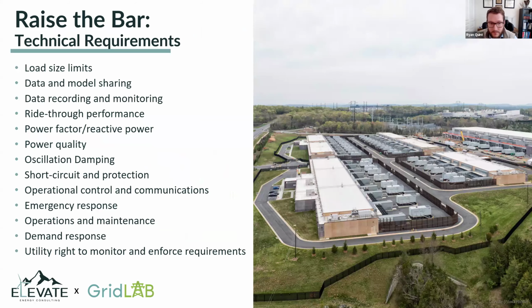Next slide. One thing we're really focused on, and were actually rather surprised by during our research, is the need to develop technical requirements for large loads. In our industry, imposing requirements on customers was, in the past, unfathomable for many. Now we're recognizing that connecting a 1,000 or 2,000 megawatt load to the system has significantly more impact than most generators on the system, in terms of tripping, oscillations, power factor, power quality, and other issues. When we started looking around, we found very few technical requirements existed for loads.